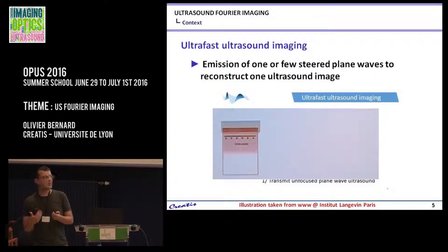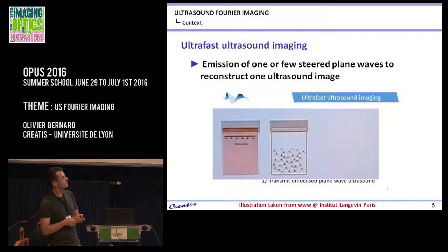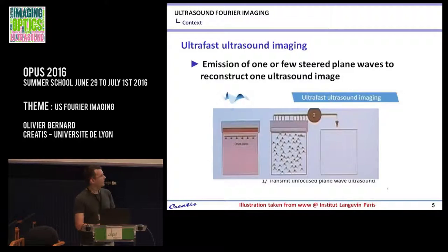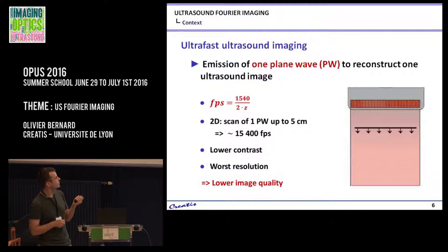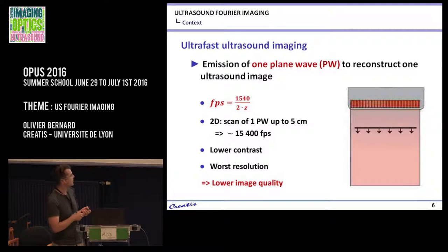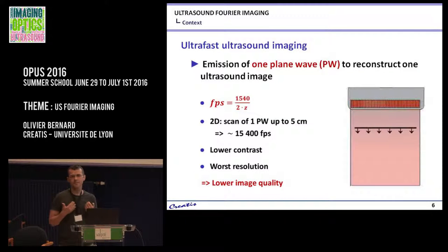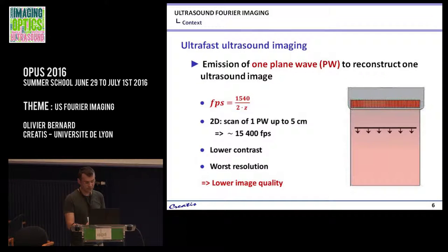You emit a plane wave, then you wait to receive the information. By doing so, you don't need anymore the number-of-lines coefficient. So actually, if you go up to 5 centimeters, you can obtain 15,000 frames per second. But of course, since you deliver less energy into the medium, you will get lower contrast and worse resolution compared to the conventional approach — globally, a lower image quality.